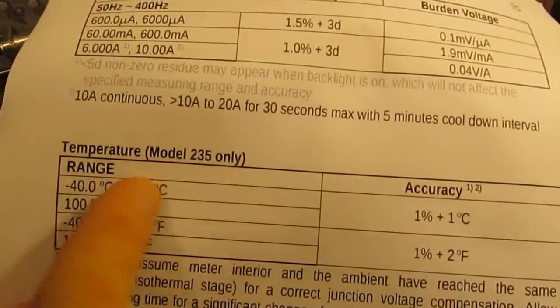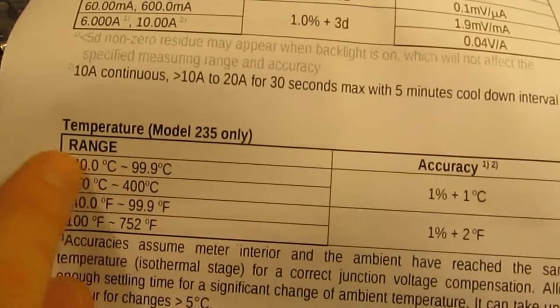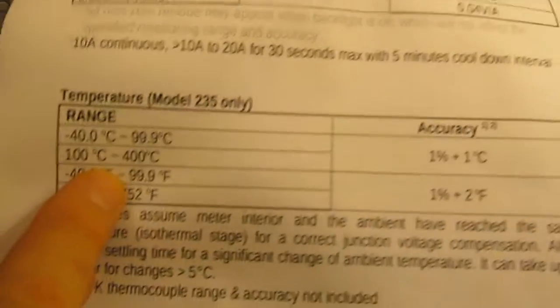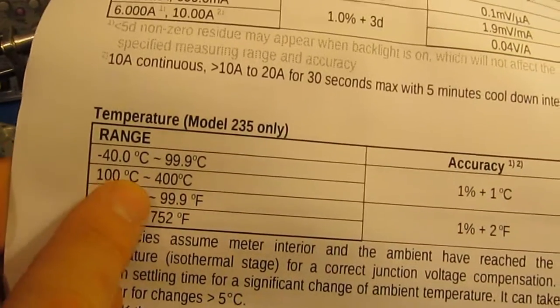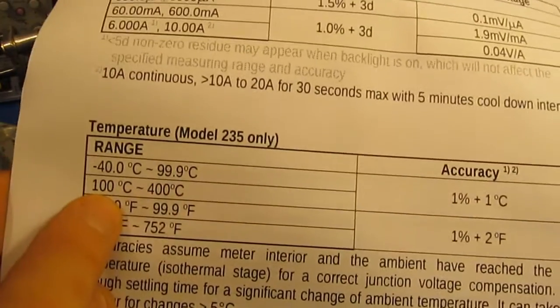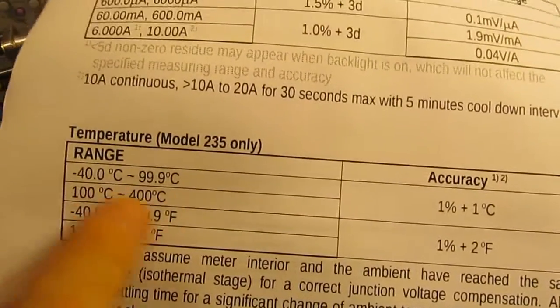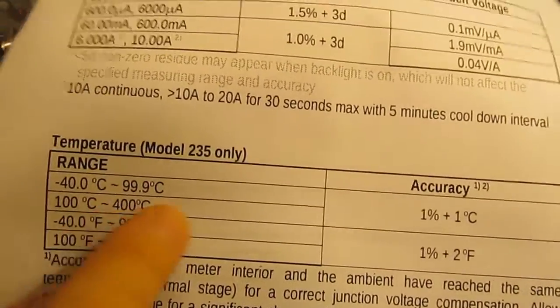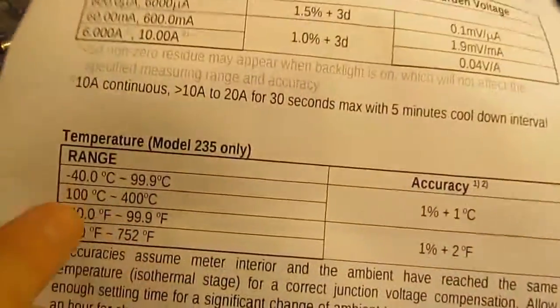Okay, so let's take a look. This is the manual that comes with the BM 235, and if we look at the temperature range we can see its maximum range is 400 degrees C. So I'm not quite sure how our member decided he can read 500 C with this.